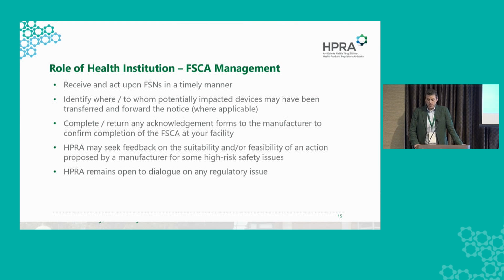We may contact you to seek feedback on the suitability or the feasibility of the action. So I think relatively recently we had an issue with an insufflator device where the manufacturer had taken an action, and it quickly became apparent through many phone calls on a Friday evening that that action was not appropriate for the healthcare system in Ireland. So I think it's important that we have that two-way communication, and as I said, for those really high-profile ones, that we have a central mechanism via the HSE to actually manage that.